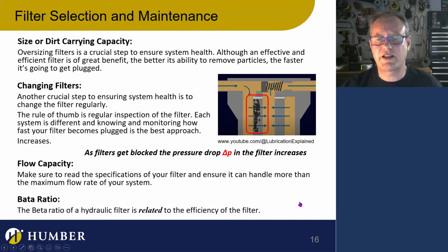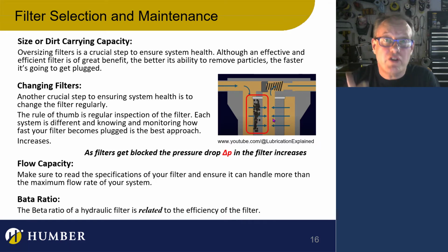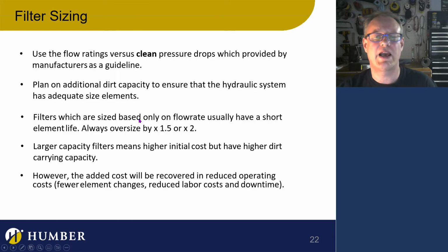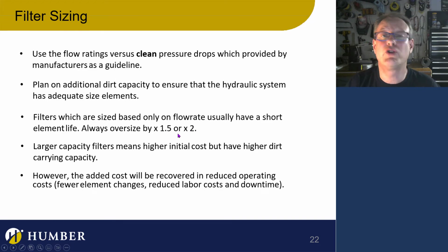And I'm just going to go back to the other slide here where I was talking about this dirt carrying capacity. Again, this is kind of the catch-22. You want your filter to collect dirt, but when it does that, it becomes inefficient. Well, just make it really big. So the larger your filter, the better. So always overrate, and you should overrate your flow rate by at least 1.5 or 2 times.